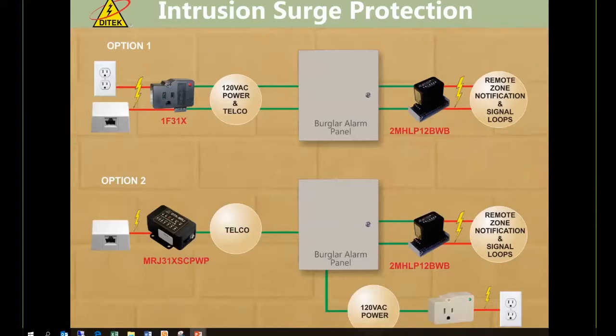And then on the other end, the modular device, 20 kA of surge protection for the remote zone notification or signal loops. On option 2, you can go with the standard phone line protector that you can utilize on the fire panels as well, the MRJ31X SCPWP for the telco line. And then on the power, you would go with the DTK-1F, a simple plug-in for 120 volt power.